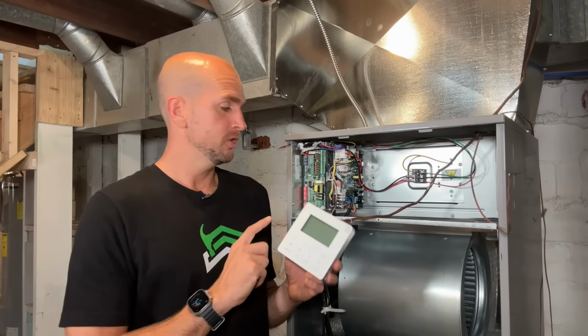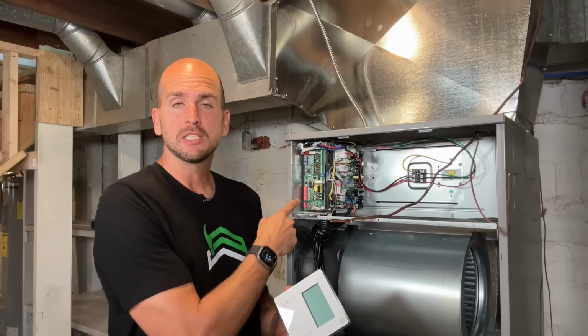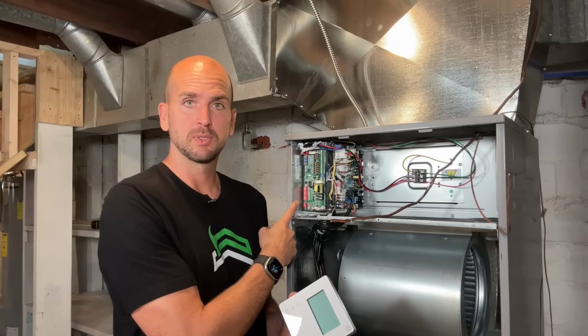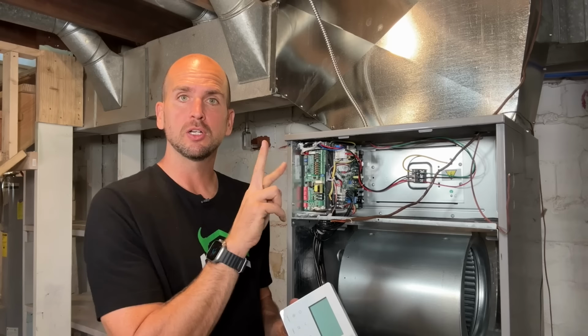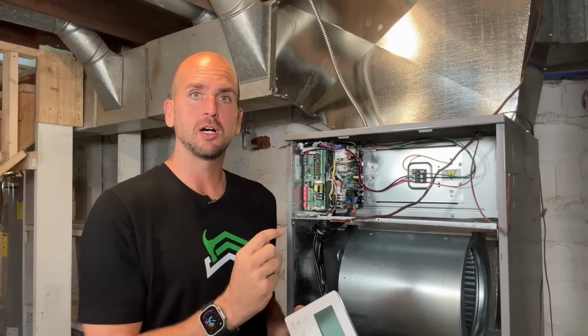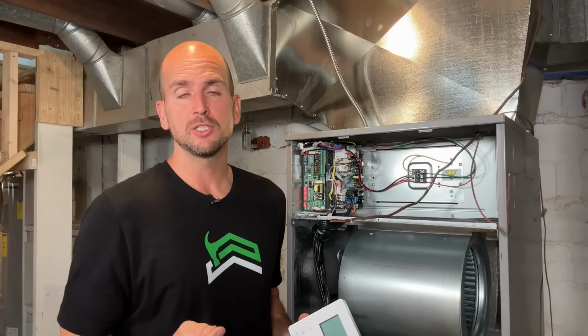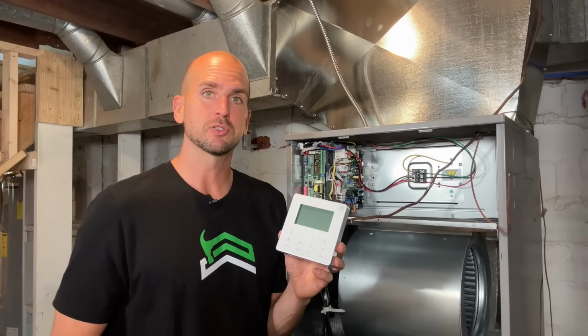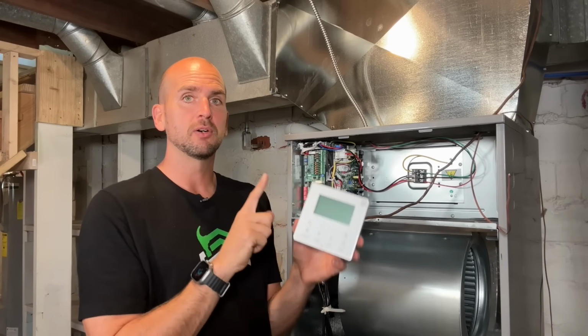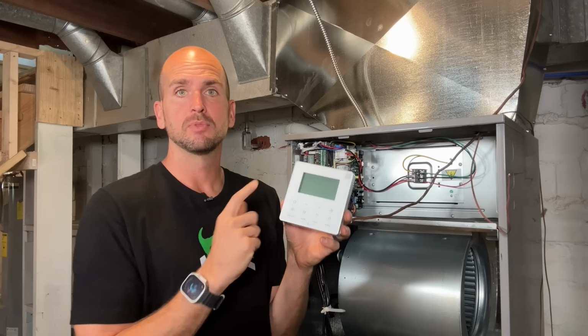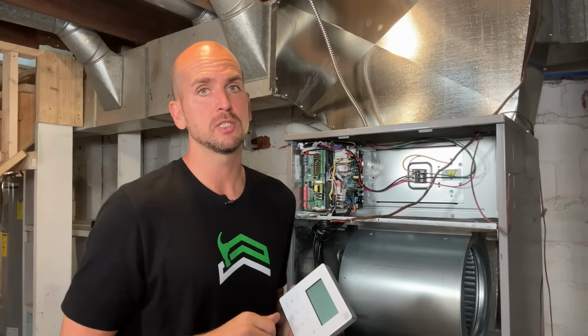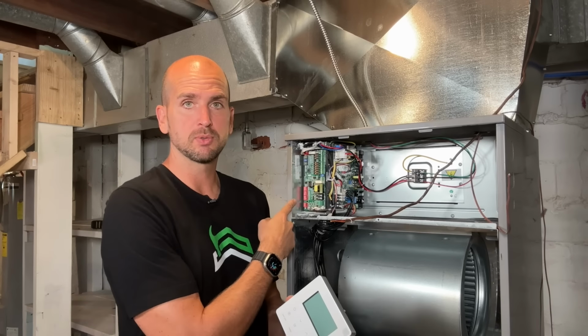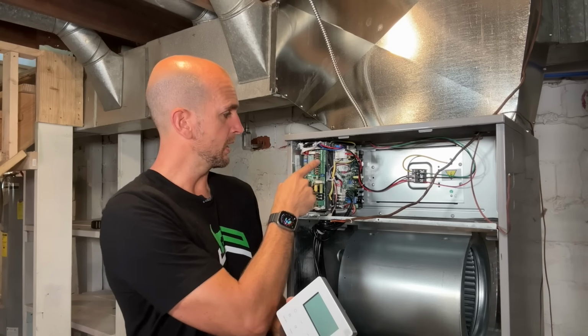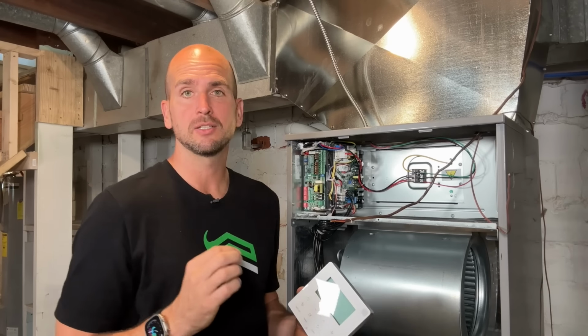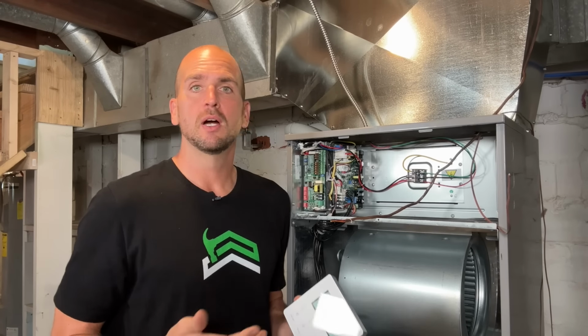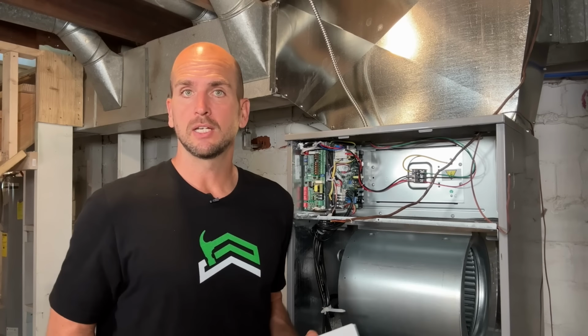And if you use this unit, you do not have to change any of these small switches. These are called dip switches. These provide you on-off, multiple different on-offs to give different configurations depending on what type of thermostat you're using. So the default scenario is this thermostat. Check the instructions if you want to use a different one, because you'll have to change the dip switches and the wiring will be quite a bit different, where you're going into your standard terminals like you might be used to on, let's say, a gas furnace with a standard air handler.